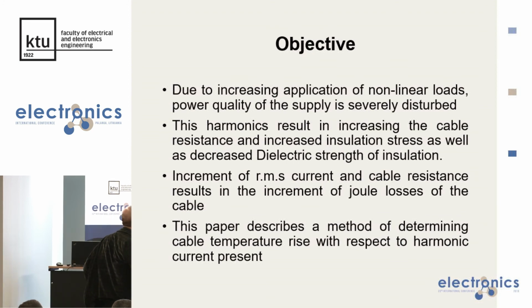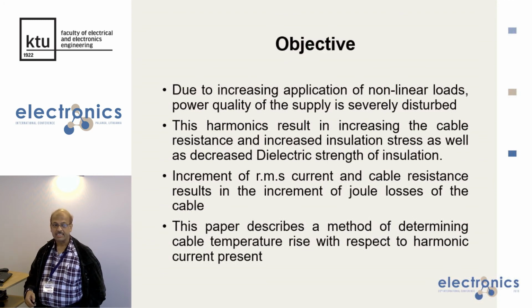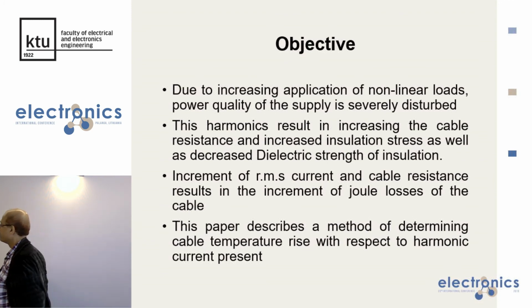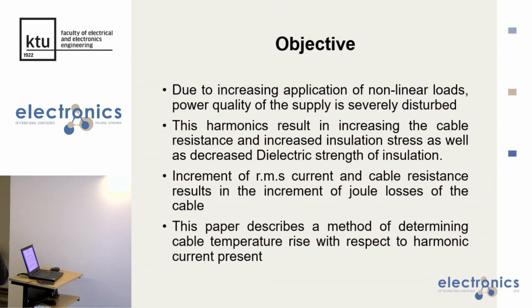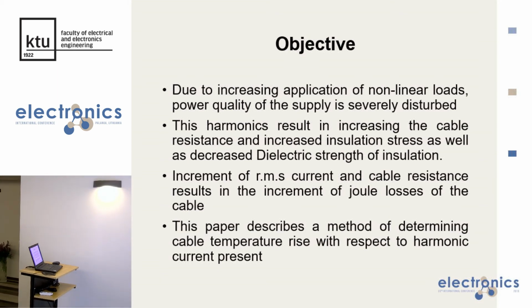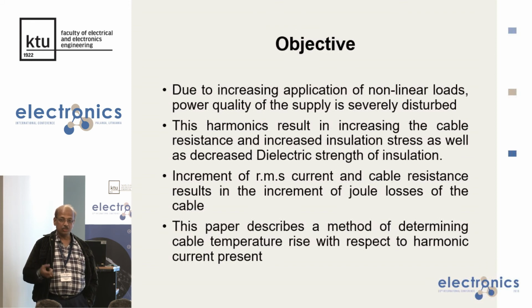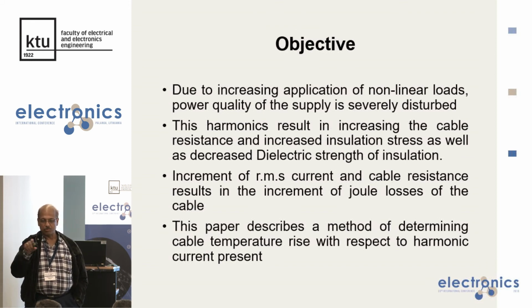These things are coming, and another important part is that it will also decrease the dielectric strength of the insulation, that is XLPE. How is that? Whenever harmonics are injected, the frequency is high, and XC is inversely proportional, 1 by 2 pi FC, so this C will create another drastic effect in the insulation of the cable.